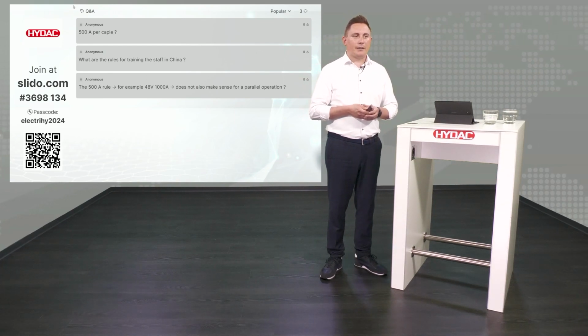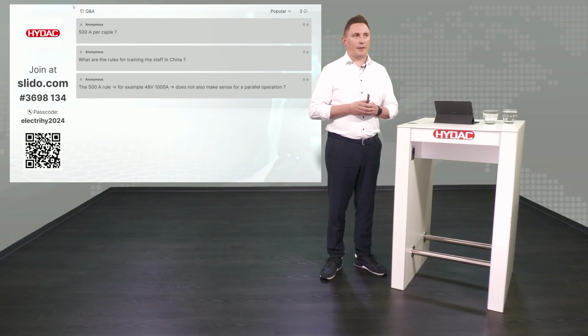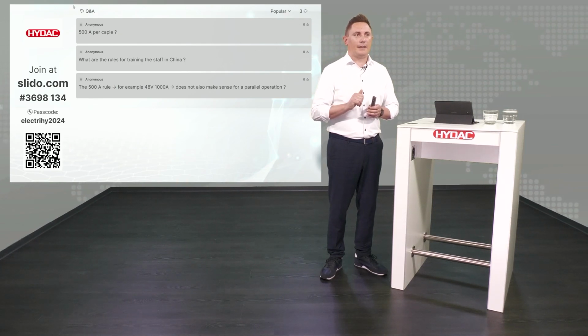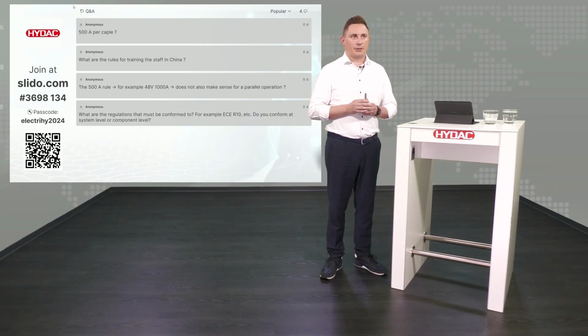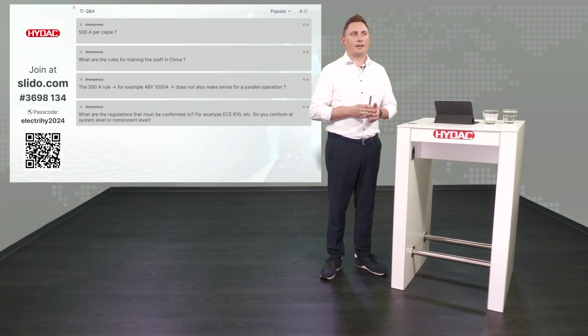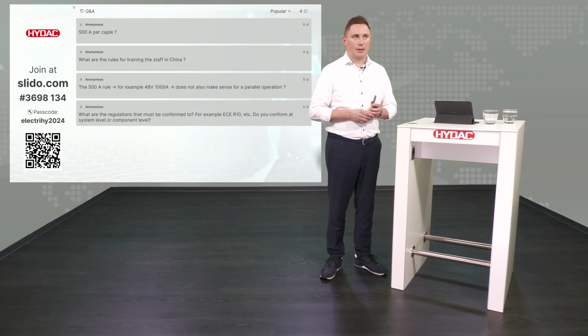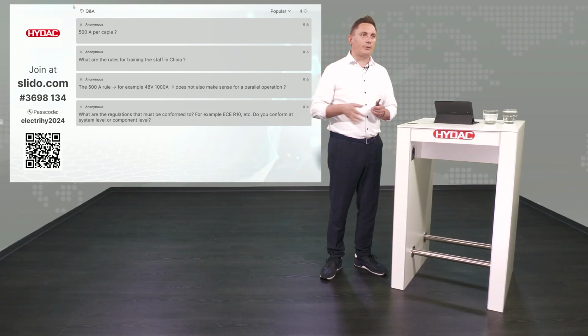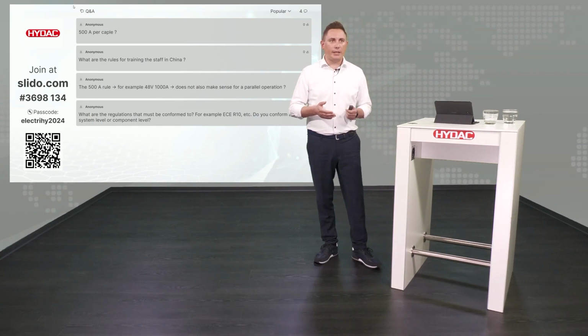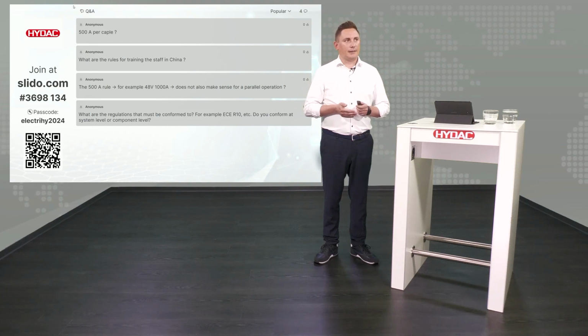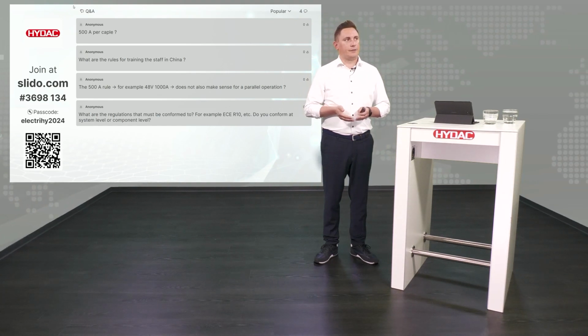That might of course make sense in certain applications, and I want to emphasize the 500 amps rule is more a rule of thumb, and there are applications where going beyond makes sense. So I don't want to say it never makes sense to have more than 500 amps in general, but in every case when we cross that 500 amps threshold, we at least take a closer look: does it make sense, or is there a more cost-efficient solution?